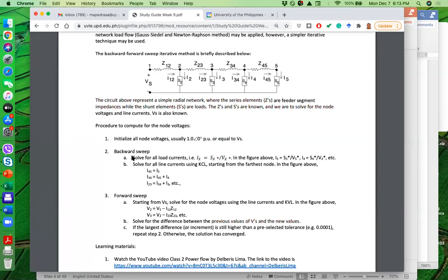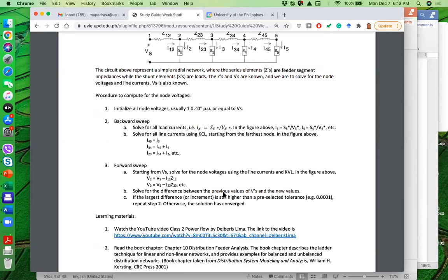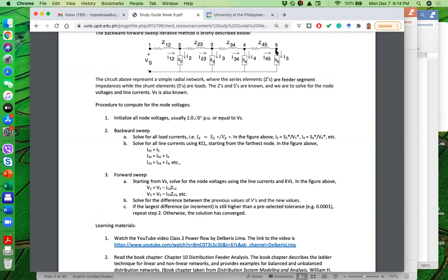Take note that our solution is iterative. After going through the forward sweep, we get new voltages V2, V3, V4, and we compare them to the previous values. Once the values are no longer changing, the solution has converged. Mathematically, we compare the new and old values of each voltage, choose the biggest increment, and compare to a preselected tolerance. When the largest increment is smaller than that tolerance, the solution has converged. The backward-forward sweep is a direct application of KCL and KVL.